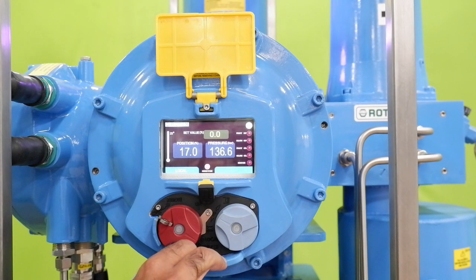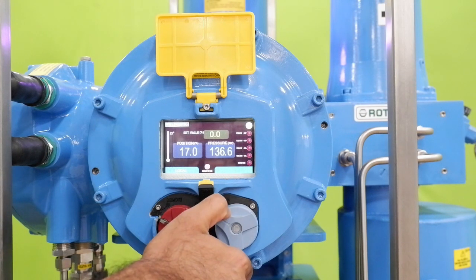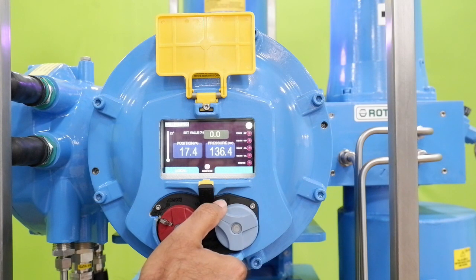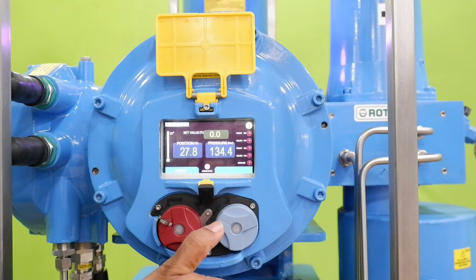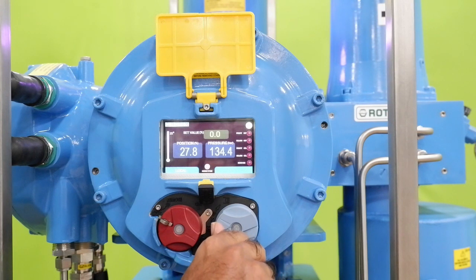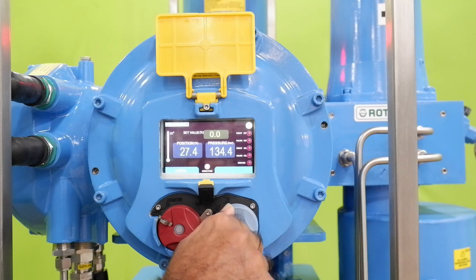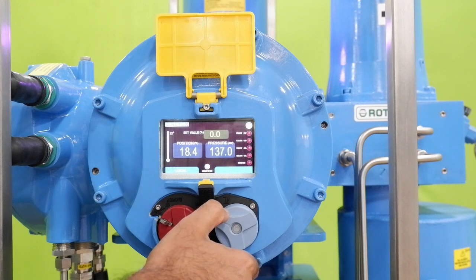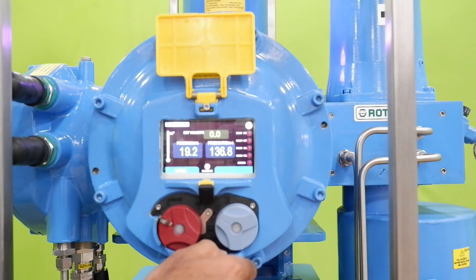Now, to change the valve position in local mode, you have to press the blue knob downwards for opening the valve. This way, you can see the valve has changed by a certain percentage. If you press continuously, the valve will change more rapidly. Similarly, if you want to close the valve, you press the blue knob momentarily. The valve changes for a certain percentage, as can be seen. So, in local mode, the valve position can be changed by a small percentage in such fashion.